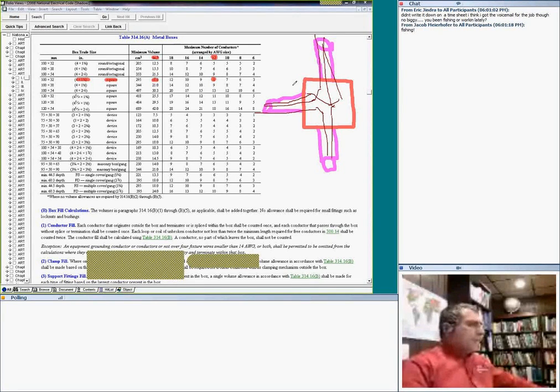Now, what happens if I need more? I need to pull more conductors. Then you have to go to a deeper box. Here's a deeper box. This can be all the way up to 30.3. I can put 13 conductors. That's my friends. That's why it's always a smart idea, when you do commercial, to put a deeper box. Don't go for an inch and a quarter. Go for at least 4 by 2.5, to give you ample room. So here's another 13 conductors I can bring to this J box.